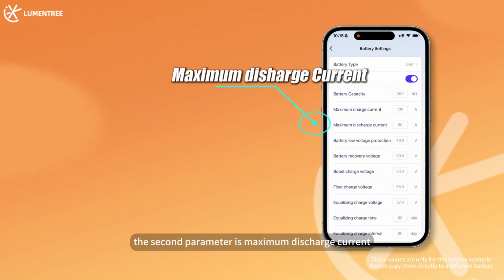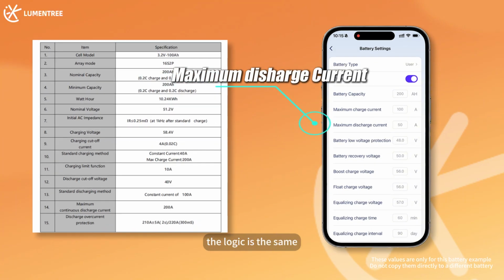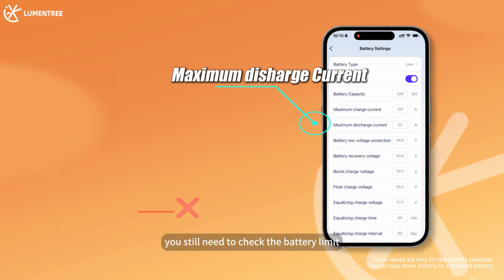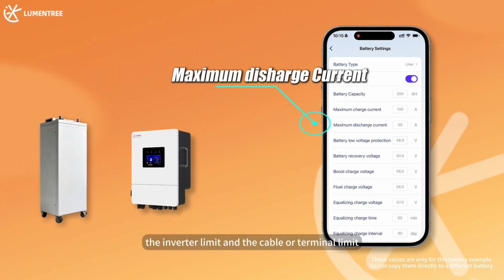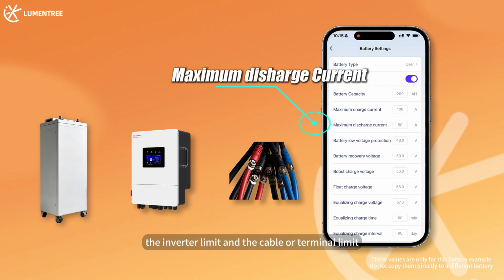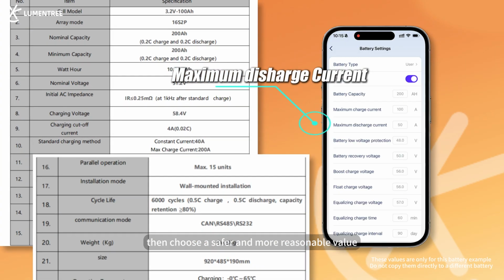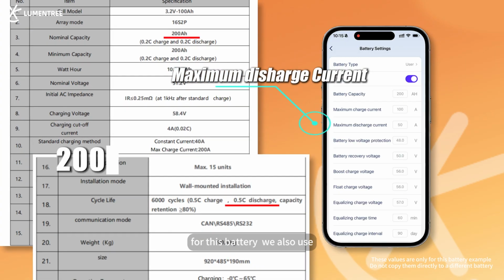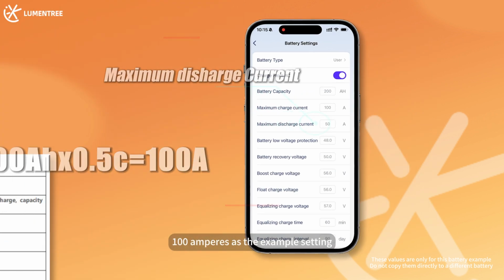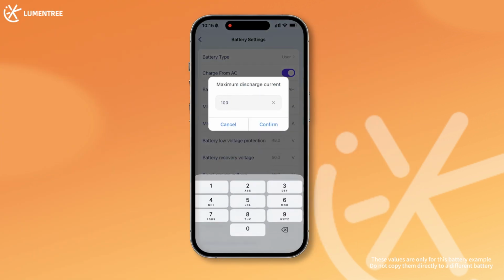The second parameter is maximum discharge current. The logic is the same. Do not copy the maximum value directly. You still need to check the battery limit, the inverter limit, and the cable or terminal limit. Then choose a safer and more reasonable value. For this battery, we also use 100 amperes as the example setting.